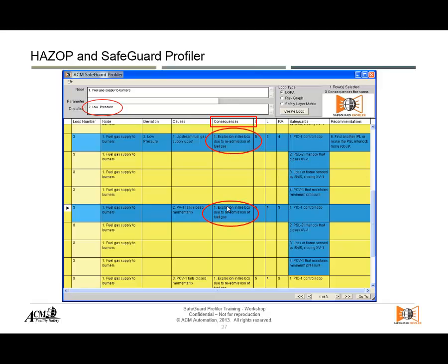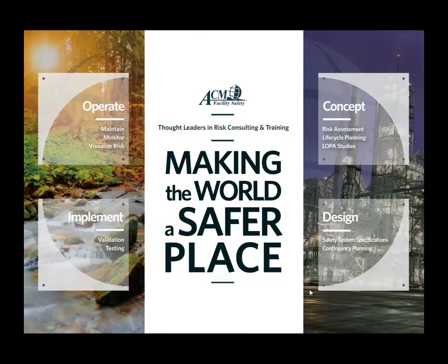Safeguard Profiler can help us if we are careful enough during the HAZOPs to identify consequences consistently, so the machine can find those patterns and tell us where to group. After going through this process — what we call the pre-LOPA work — we create scenarios that now include several sources of risk, giving us a better analysis and a better understanding of the sources of risk working toward that severe consequence that we don't want to happen.